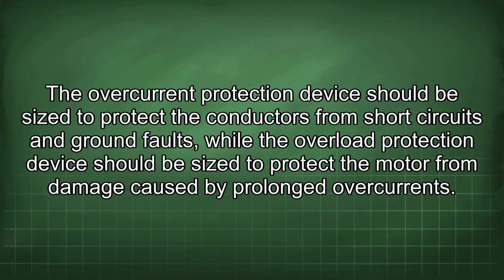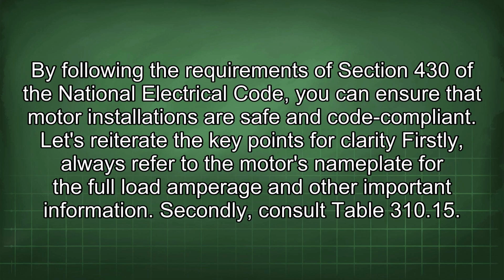The overcurrent protection device should be sized to protect the conductors from short circuits and ground faults, while the overload protection device should be sized to protect the motor from damage caused by prolonged overcurrents. By following the requirements of Section 430 of the National Electrical Code, you can ensure that motor installations are safe and code compliant. Let's reiterate the key points for clarity.